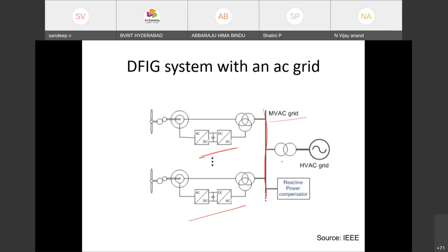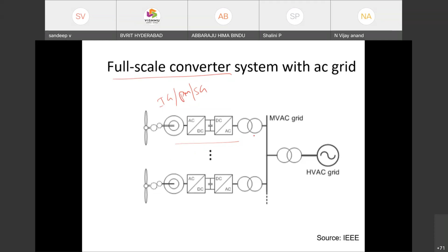And similarly you can exercise with DFIG also. This is DFIG 1 and DFIG 2, and you have a common medium voltage AC grid, and through a transformer connected to the high voltage AC grid also. So that way it is also possible. And this is full scale, not DFIG - directly the generator can be an induction generator, PM generator, or synchronous generator. Three possibilities are there. So you have an AC to DC rectifier, and then inverter, and then transformer. You can have a common bus bar, transformer connected to utility.